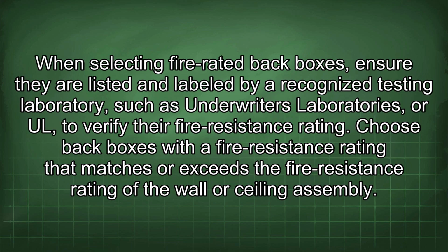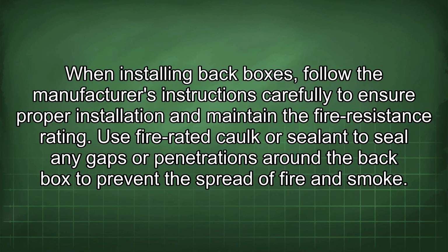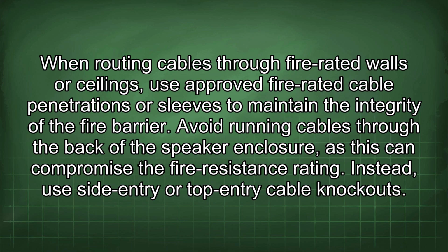When selecting fire-rated back boxes, ensure they are listed and labeled by a recognized testing laboratory such as Underwriters Laboratories or UL to verify their fire resistance rating. Choose back boxes with the fire resistance rating that matches or exceeds the fire resistance rating of the wall or ceiling assembly. When installing back boxes, follow the manufacturer's instructions carefully to ensure proper installation and maintain the fire resistance rating. Use fire-rated caulk or sealant to seal any gaps or penetrations around the back box to prevent the spread of fire and smoke. When routing cables through fire-rated walls or ceilings, use approved fire-rated cable penetrations or sleeves to maintain the integrity of the fire barrier.